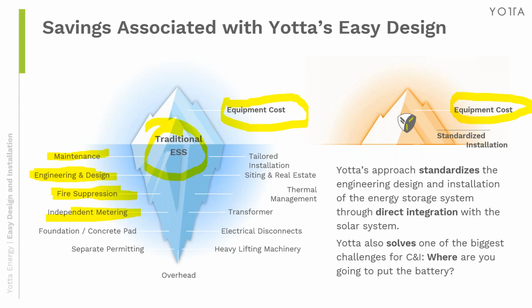As an AC coupled system, now you've got independent metering. Our DC coupled system sits on the roof. An outdoor system would require some kind of foundation and separate permitting because it's on the AC side, not the DC side, due to its size. You need lifting equipment. There are a lot of hidden or unknown costs: electrical disconnects, transformers, and thermal management. There's a lot of liquid cooling for some of these battery systems, since it's an active system, not a passive system like the Yotta solution.